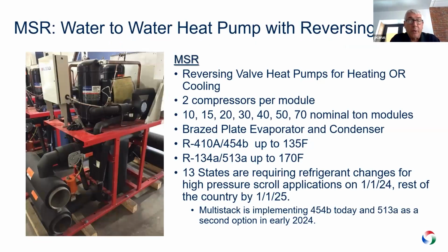The MSR, reversing valve heat pump for a heating and cooling application, typically 2 compressors per module, anywhere from 10 to 85 tons now, using a brazed plate evaporator and a condenser. Recent developments would say in many parts of the country, 13 states to be exact, effective January 1st of 2024, 410A will no longer be available. The rest of the country will still have the opportunity to use 410A, but we're moving to 454B in addition to 410A, and creating hot water up to 135, perhaps 140 degrees Fahrenheit, depending on the rest of the conditions in the facility.